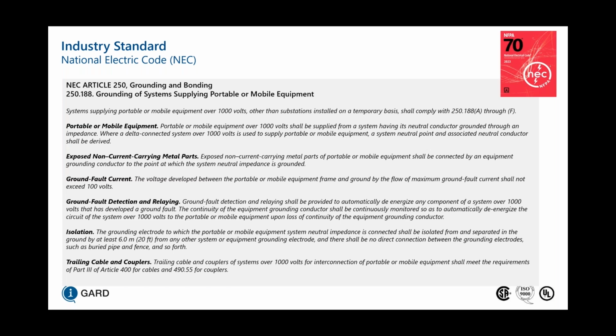And where a delta connected system over 1,000 volts is used to supply portable or mobile equipment, a system neutral point and associated neutral conductor shall be derived. Exposed non-current carrying metal parts have to be properly grounded to the point at which the system neutral impedance is grounded. And in terms of ground fault current, the voltage developed between the portable equipment and ground by the flow of maximum ground fault current shall not exceed 100 volts.